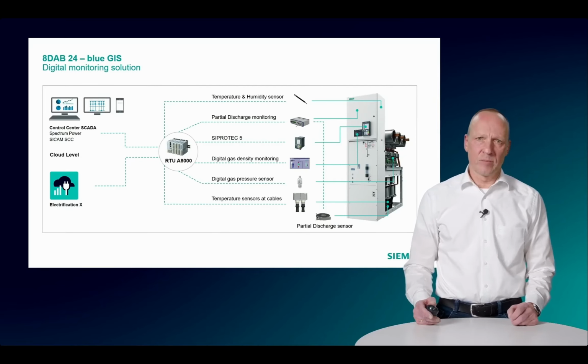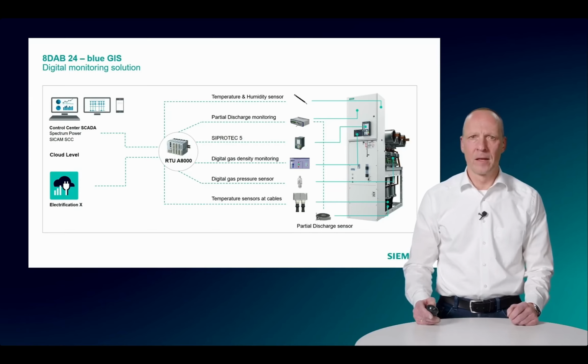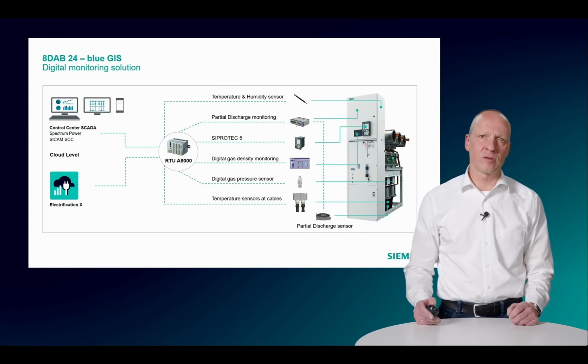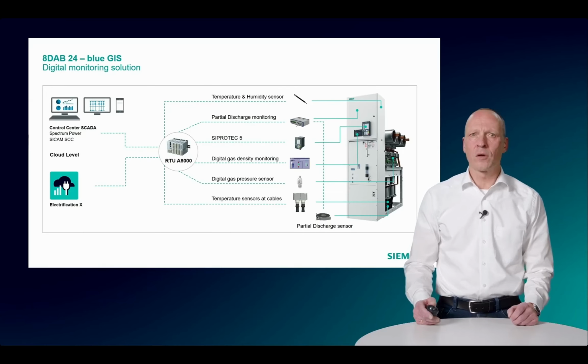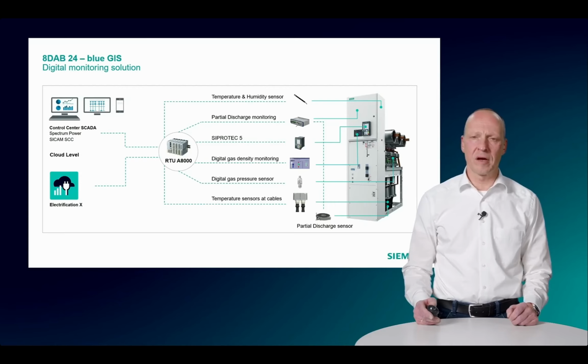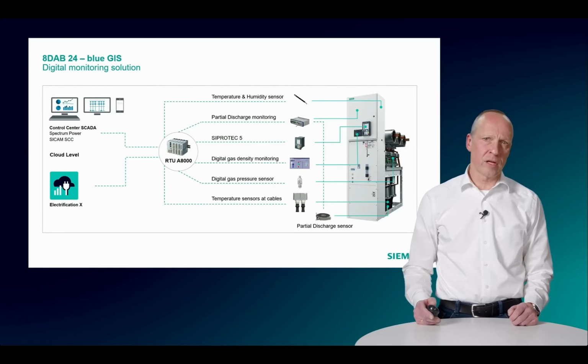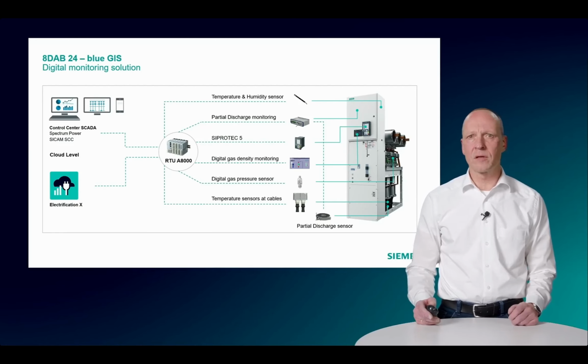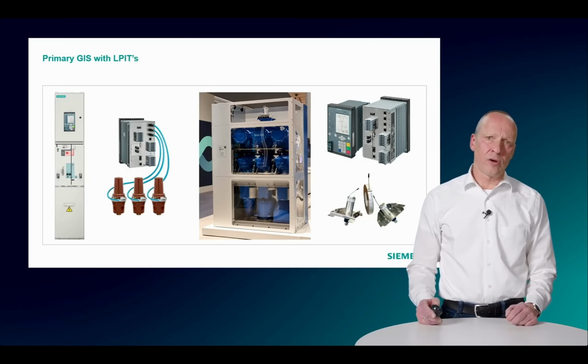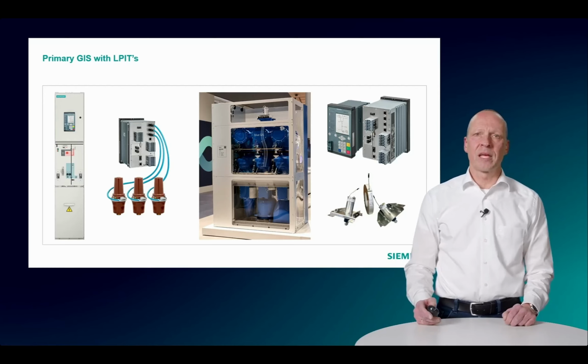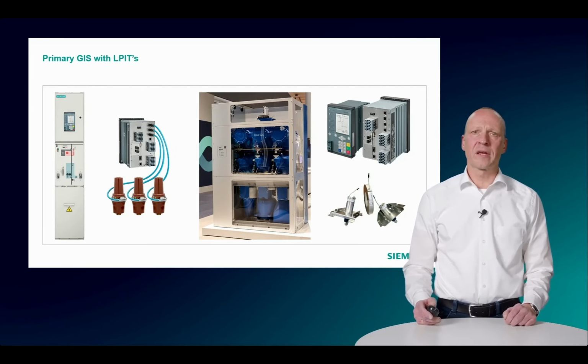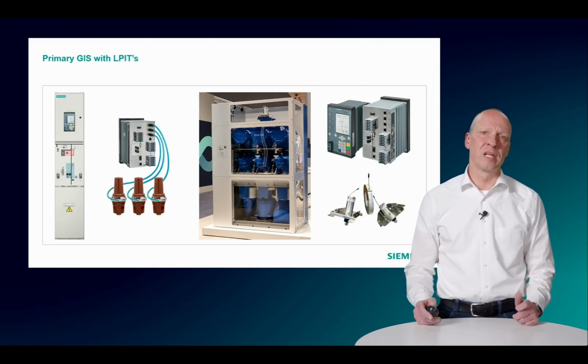The gas density monitoring requires digital gas pressure sensors per gas room connected to the A8000 gateway, where further analytic algorithms are implemented. Load flow monitoring can be provided based on current and voltage transformers connected to the protection relay from our SIPROTEC 5 family. In the past, current and voltages have mainly been measured using conventional current and voltage transformers.